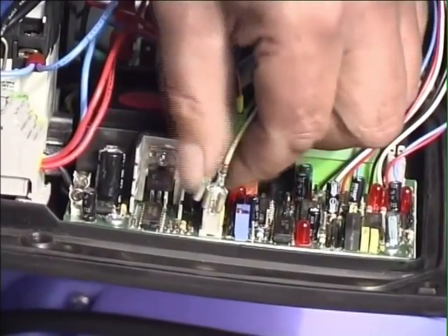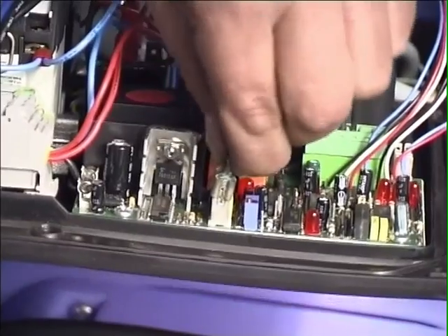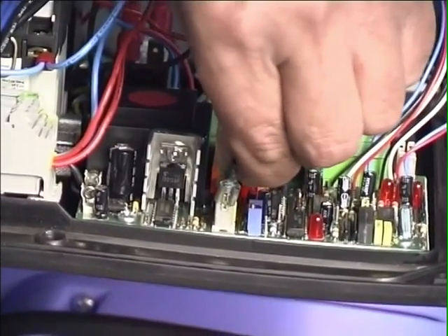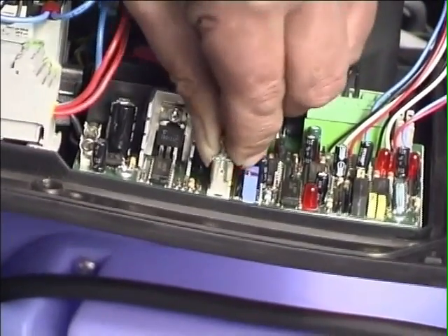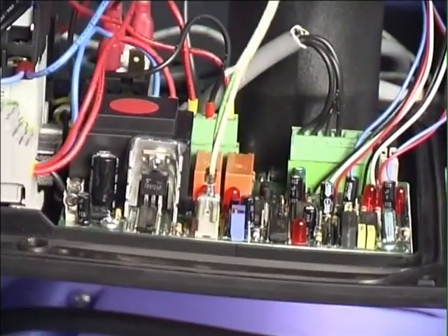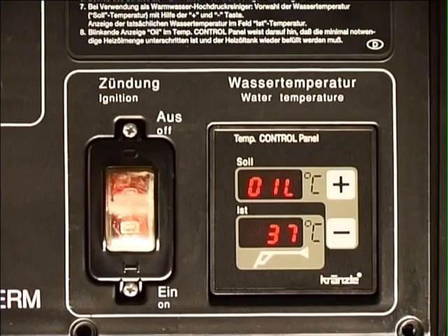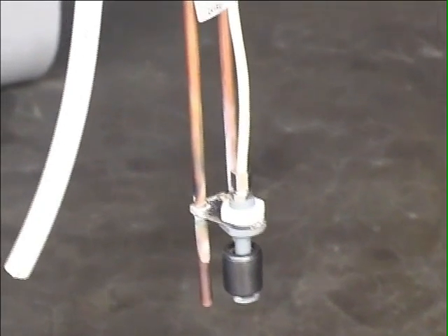Starting autumn 2003, the machines have been equipped with an optical flame monitoring. You can find information about it in the chapter The New Digital Display. If there is enough fuel in the tank and the error message oil still lights up, the floater may be sticking, a cable is defective, or the supply tubes are clogged.